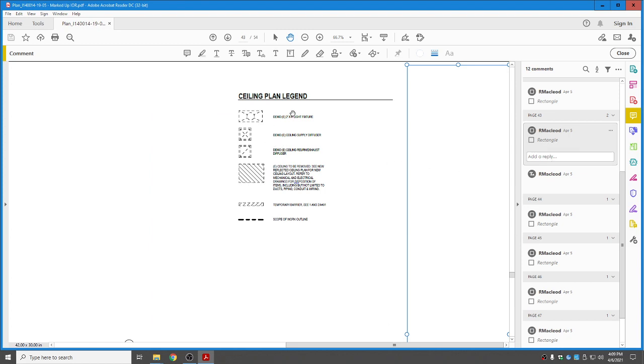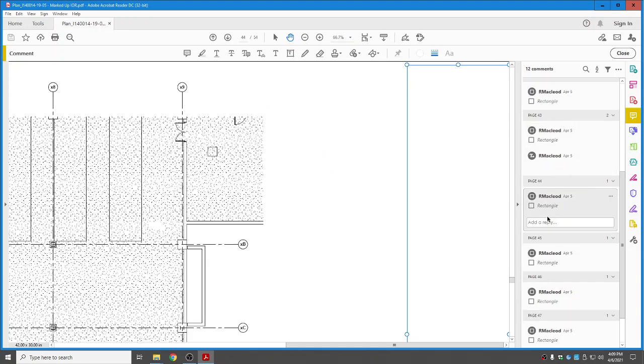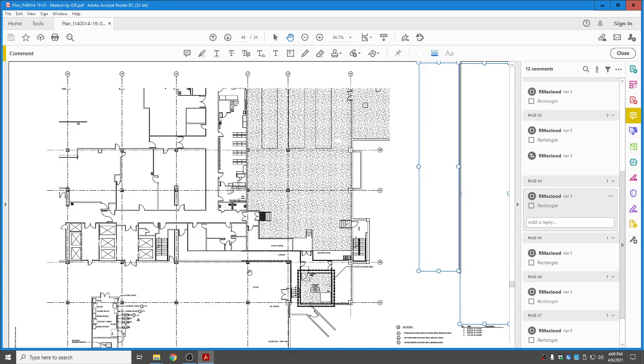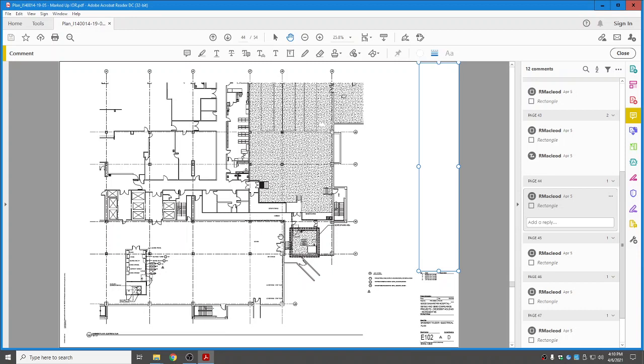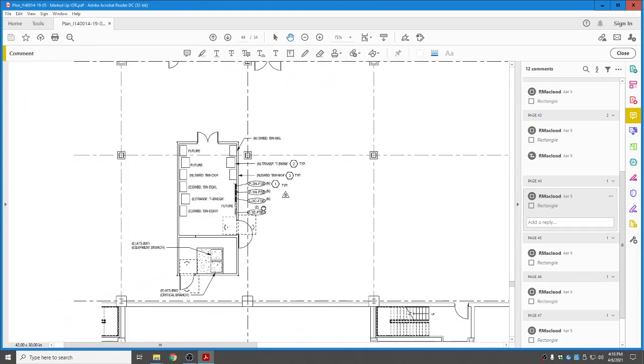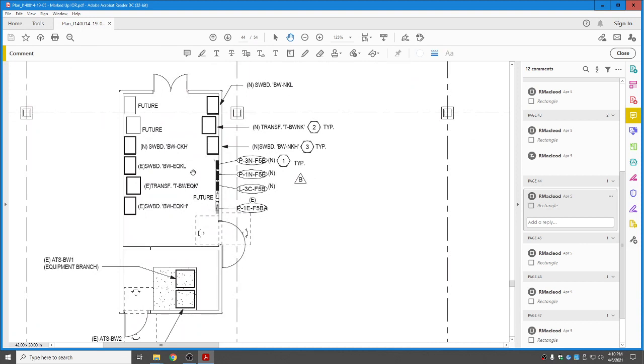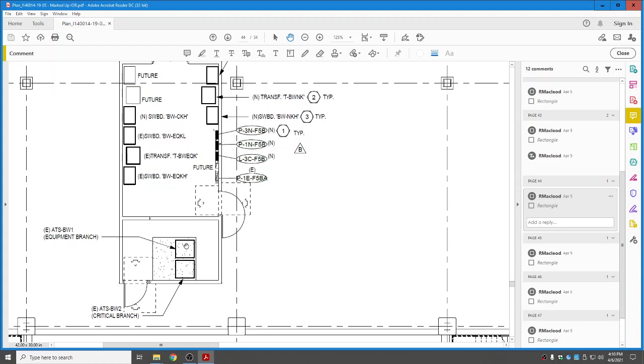Now here's a ceiling plan legend showing all the devices in the ceiling that will be removed. Here's a floor plan down in the basement. Let's zoom in on one of our electrical rooms. This particular electrical room is 1 hour rated. You can see our transfer switches down here on the bottom. Critical branch and an equipment branch transfer switch are providing power up to our electrical panels. You see the ones with the N are normal power, and the C would be critical, and the E would be equipment panels.